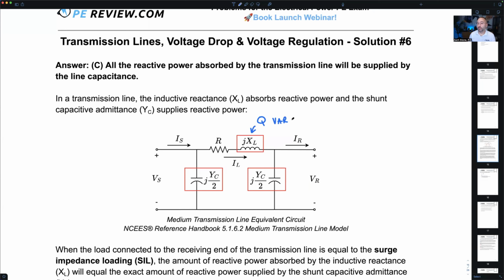That reactive power has to come from somewhere. If the load on the receiving end of our transmission line is equal to that vocabulary word, the surge impedance loading, then all of the reactive power absorbed by the reactance of the transmission line... And remember, this is just modeling the what? That's just modeling the conductors on the transmission line. This R, this jX_L, even the shunt admittance, that's the properties of the actual conductors themselves. When you drive along the road and you see the big transmission lines, maybe down the highway, this just models the big transmission line conductors. So all the reactive power absorbed right here, 100% of it, the exact amount, gets supplied by the shunt admittance.